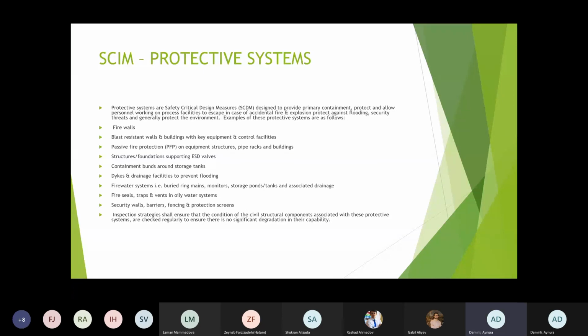This is a protective system for equipment, but the protective system is inspected and monitored by the civil structural integrity management part: pipe racks and buildings, structures, foundations supporting equipment, shutdown valves, containment bunds around storage tanks, dikes and drainage facilities to prevent flooding, fire water systems, like buried ring mains, monitors, storage ponds, tanks, and associated drainage, fire seals, traps, and vents in oily water systems, security walls, barriers, fencing, and protection screens. Inspection strategies shall ensure that the condition of the civil structural components associated with the protective systems is checked regularly to ensure there is no significant degradation in their capability.